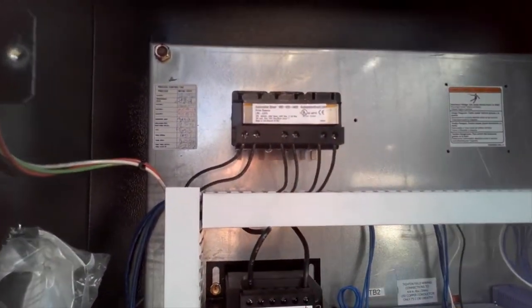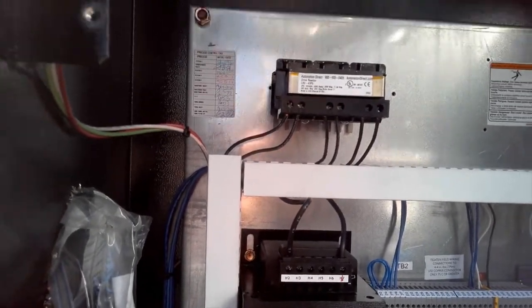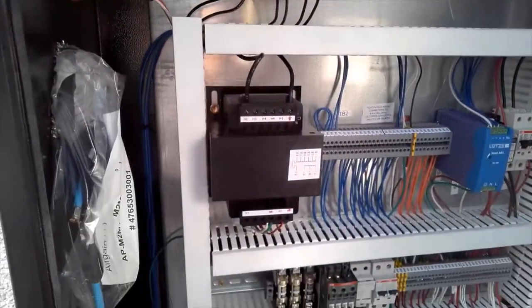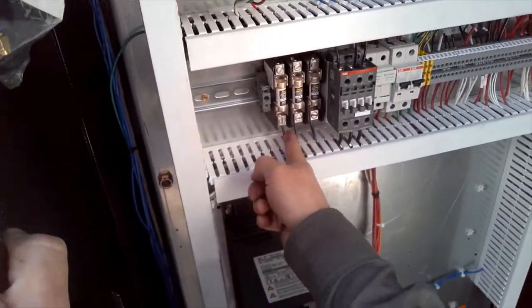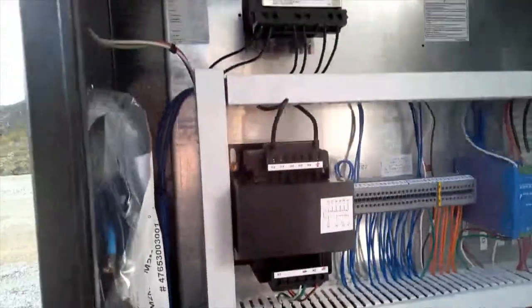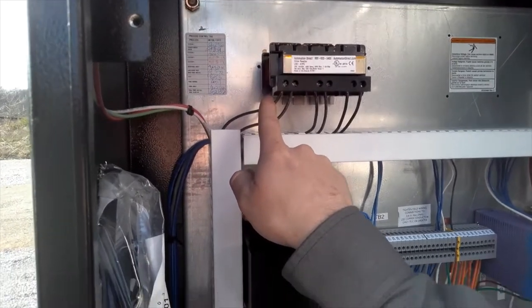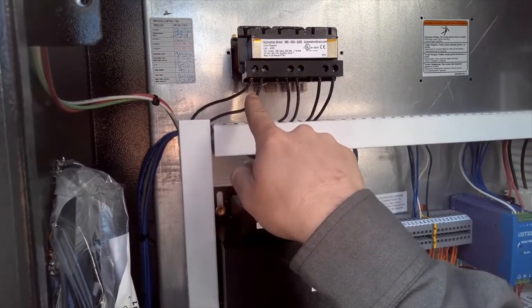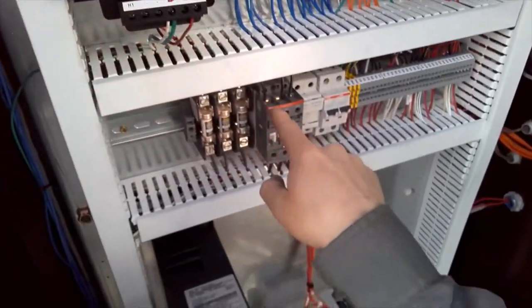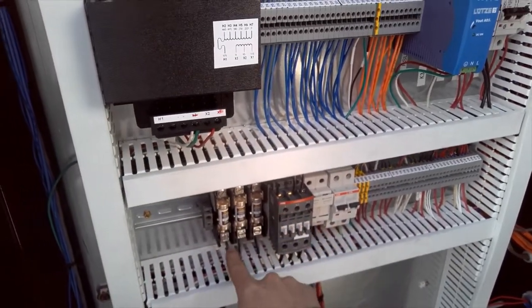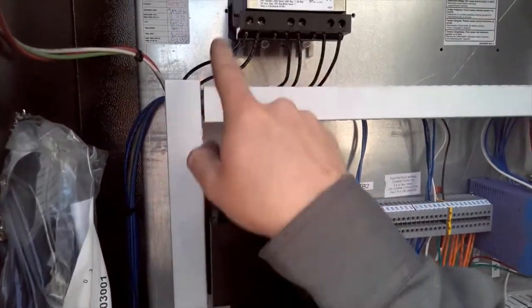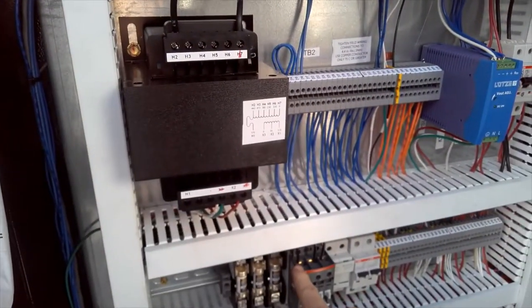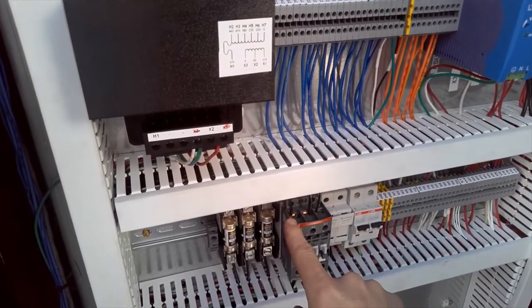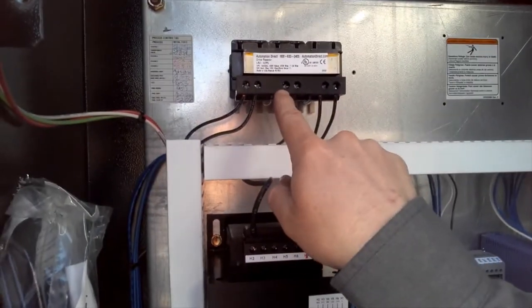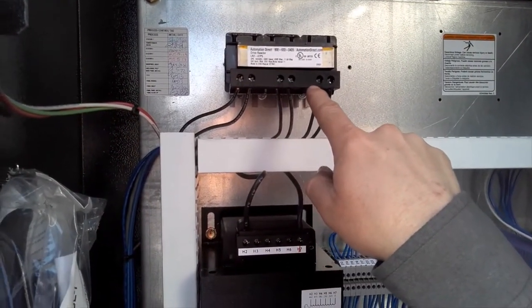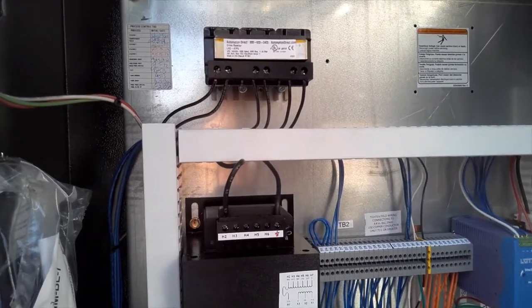All right, so now you can see we've got this line reactor mounted. Essentially, we're going from the bottom of the fuse, downstream of the fuse, into A1, and that's the line side, and then the load side from A2 into the top of the contactor. Before, it was just going directly into here; now it's going into the line reactor, out of the line reactor, into the contactor, and we've done that for all three legs. Into B1, out B2. In C1, out C2. And that's how it goes.